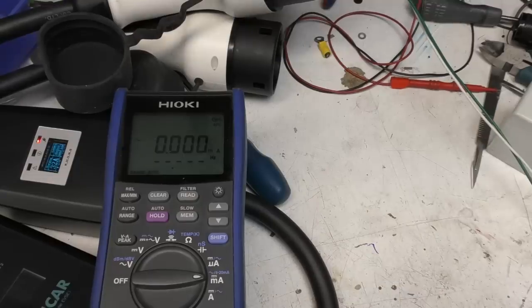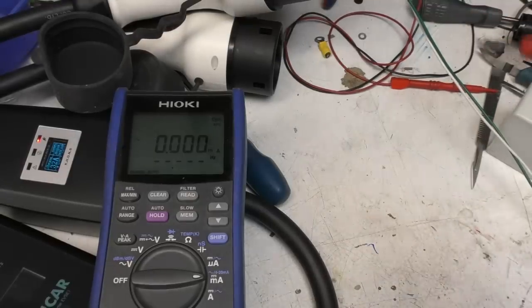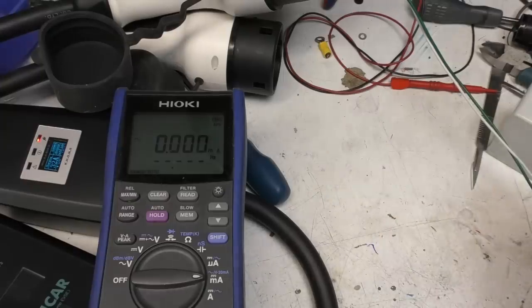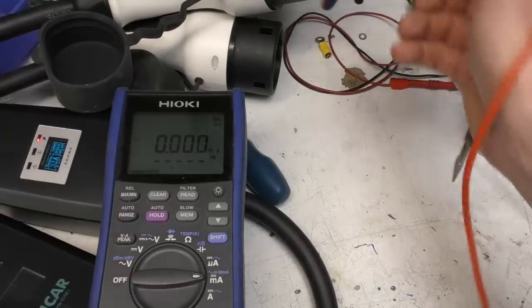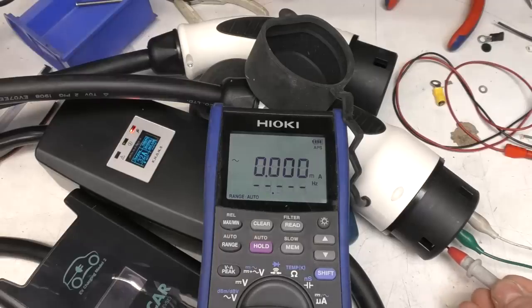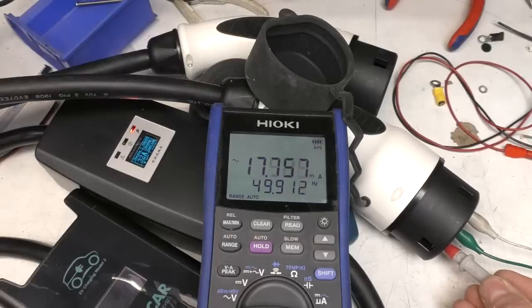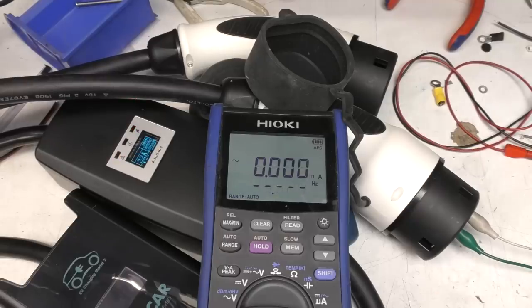So what I'm going to do is reduce the input voltage, and then as I increase the voltage that's also going to increase the leakage current. So we'll see at what point it actually trips. So I've set the pilot signal to turn the output on. So this is the Khons unit, 17 milliamps, 20, so that's tripping out at about 20 milliamps, that's fine.